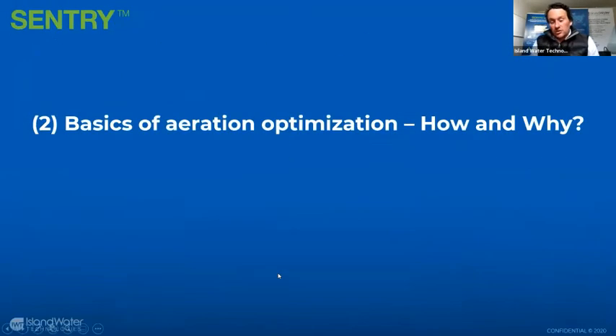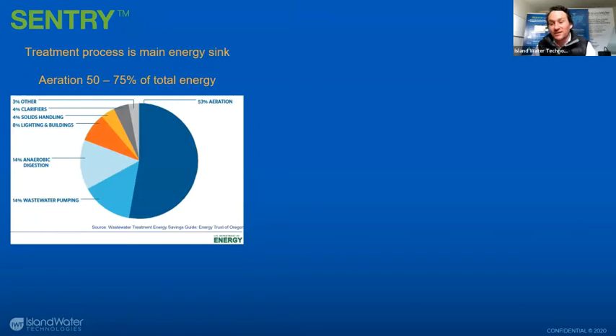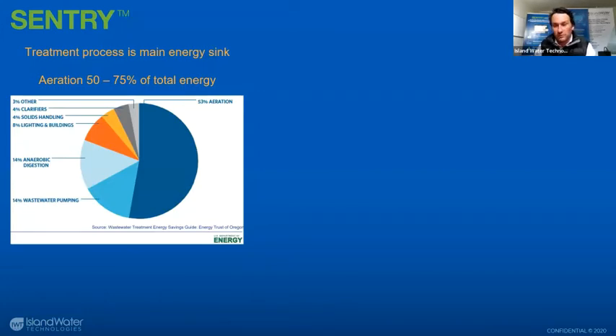Now for aeration optimization. This graph represents energy consumed by different processes at a traditional wastewater treatment plant. Aeration is the largest consumer — 53% of wastewater treatment plant energy is used for aeration, and that number can be as high as 75% of total energy. That's where a lot of the energy and operational costs go, making it the clear low-hanging fruit for optimization.